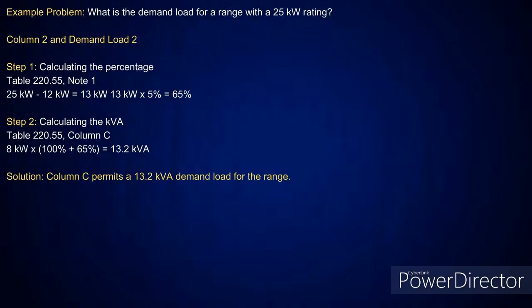So basically that's 100% of the load. I'm going to take 100% plus 65, that's 165% I'm adding for each additional load. Then I have one range that I did for the 12 kW. Come across it, it tells you it's rated at 8 kW in column C. So I take the 8 kW at 165%, and that'll give me 13.2 kVA or 13,200 VA.